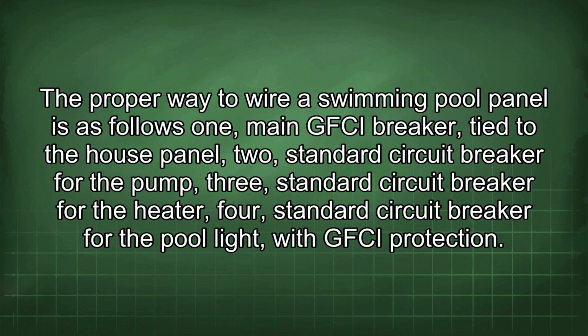The proper way to wire a swimming pool panel is as follows: 1. Main GFCI breaker tied to the house panel. 2. Standard circuit breaker for the pump. 3. Standard circuit breaker for the heater. 4. Standard circuit breaker for the pool light, with GFCI protection.